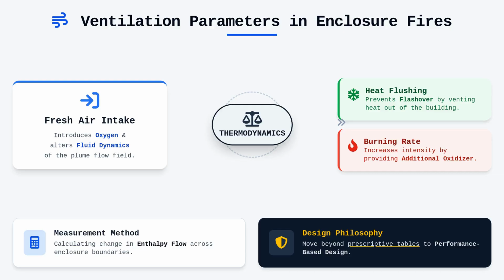We measure the dilutive effects of ventilation by calculating the change in enthalpy flow across the boundaries of the enclosure. Mastering these principles allows you to develop site-specific performance-based design criteria that stand up to peer review. It is not enough to rely on prescriptive tables found in codes. You must understand the underlying science to adapt those requirements to non-standard fire scenarios.